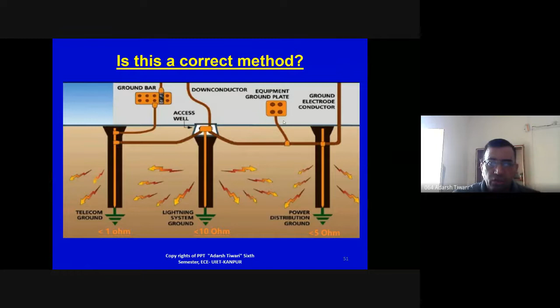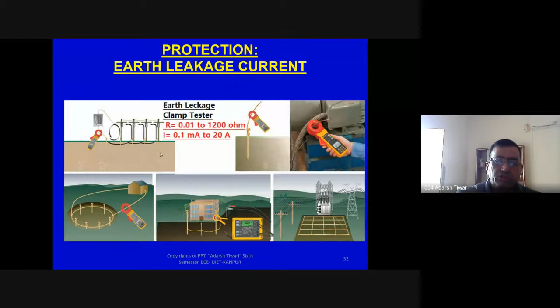But how to check whether the grounding and the connection are proper, or whether some leakage current is going on? There is different equipment available, like the earth leakage clamp meter. If you put that meter on that grounding system, it will automatically read the grounding of that equipment, the earth resistance of that equipment.